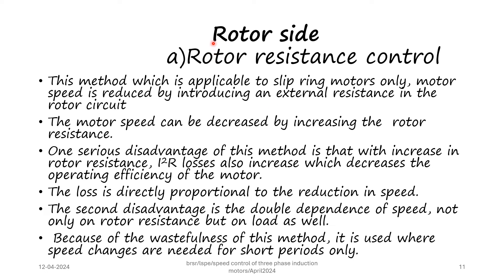Speed control of three phase induction motors from the rotor side involves two methods: rotor resistance control and slip power recovery schemes. This rotor side control is possible only for slip ring induction motors, not squirrel cage induction motors. In rotor resistance control, an external resistance is introduced in the rotor circuit to change the motor speed. One serious disadvantage is that with increased rotor resistance, I²R losses also increase, decreasing operating efficiency. The losses are directly proportional to the reduction in speed. Additionally, the speed depends not only on rotor resistance but also on load.